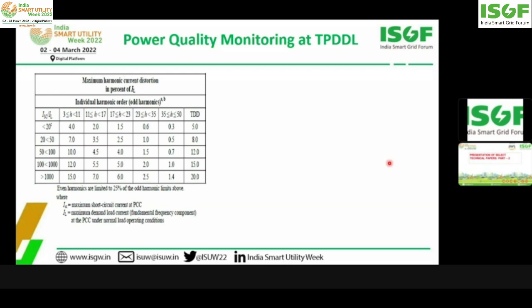Now, moving on, I'll explain the way we have carried out our study. We selected some different category industries to carry out our study and followed DRC and IEEE standards in this study. This is IEEE 519/2014 standard on power quality. Here we can see that these are the limits mentioned for current harmonic distortion. Here one important point is that TDD, which is the current harmonic limits, vary from consumer to consumer. We cannot apply the same limits for all the consumers.